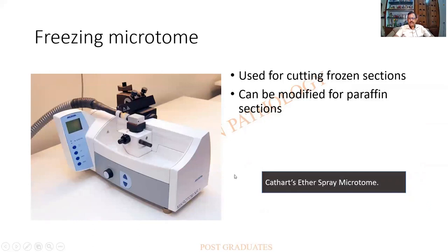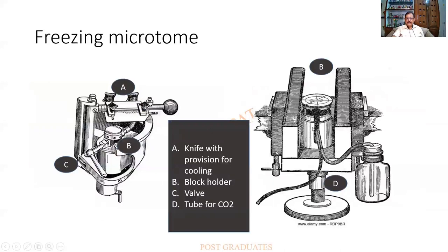The freezing microtome uses ether as a spray to provide freezing. It was used for rapid intraoperative diagnosis and for demonstration of fat while the patient is on the operating table. Instead of paraffin wax, ice or ether provides mechanical support for the tissue block. There is a block holder where the tissue block is placed, a knife holder with adjustable angles, clamps for holding the knife, and a tube connected to a carbon dioxide cylinder — the CO₂ freezes the tissue block, making it mechanically sturdy.